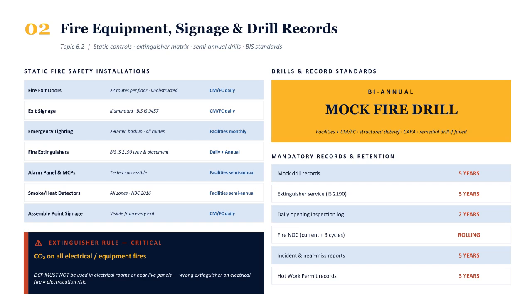Fire extinguishers, type and placement per BIS IS 2190. Fire alarm panel and manual call points. Smoke and heat detectors in all zones. And assembly point signage visible from every exit route. Now the critical extinguisher rule, CO2 on all electrical and equipment fires. DCP must not be used in electrical rooms or near live panels. Using the wrong extinguisher on an electrical fire creates an electrocution risk.